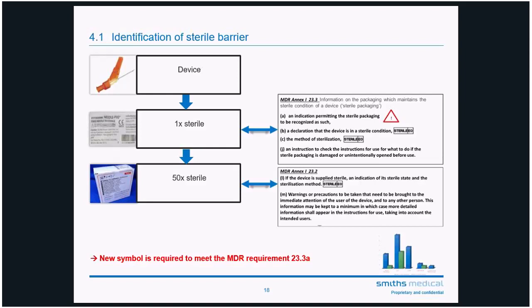And when you map the relevant sections of MDR next to those layers, what is the sterile layer here, where you have section 23.3, and where you have the multiple or the general labeling layers, that is 23.2, you can see that there is a duplication of requirements. So a declaration that the device is in a sterile condition and the method of sterilization has to be provided on both. So the good old principle, as you can see from AMDD, to use the sterile EO symbol, for example, to identify the sterile barrier doesn't work, because you still have to provide the methodology of sterilization and its status on the general layers of labeling.